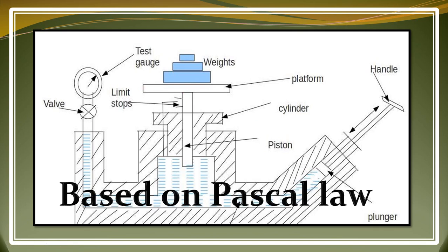Now we connect our test gauge and open the valve and put the weight again on the platform. Now the piston is not moving, so when we apply the weight, it exerts the same pressure as we previously applied with the handle. So the pressure output is exerted in every direction with the same force. So the pressure P is also applied to this gauge and we can read this from its pointer. We check whether the value of P and the output pressure of this gauge match. If it is different, we change the gauge value and correct the gauge value with the help of our first pressure P. So it is a very precise instrument.